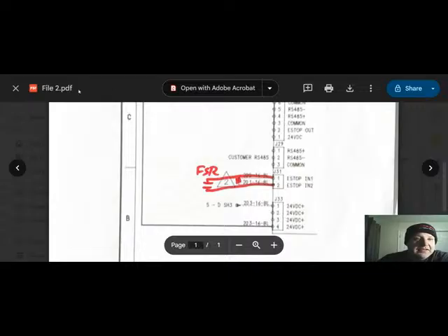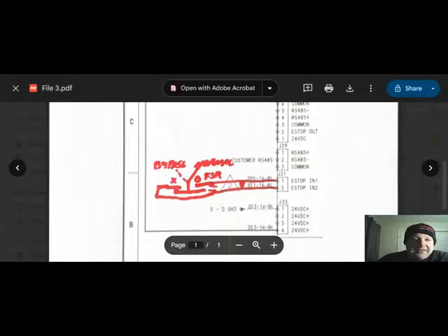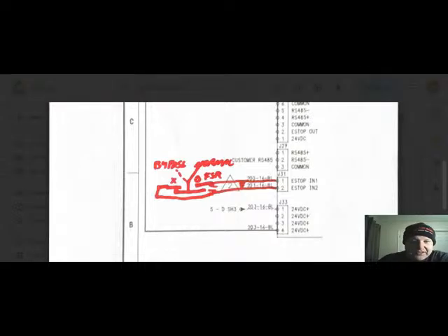So again, we can go to our next level, which would be adding that bypass. And this is going to be in series. You can see this is poorly drawn, but this is normally open. When the switch is in the normal position, this is going to be open. We are maintaining the loop with this right here. We switch this to bypass. This is going to close and maintain the loop. And then it doesn't matter what happens with this fire suppression relay. It's not going to make any difference because the loop's being maintained through this manual switch.